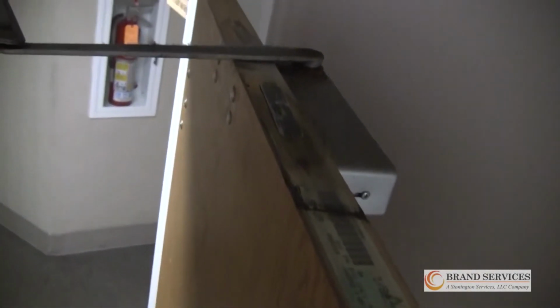First we verify that either or both the door and frame are labeled. Doors and frames are required to be labeled and listed. This stairwell door is required to be 90 minutes or 1.5 hours. Frame labels are not to be painted over. Here you'll find a frame label that has been painted over and is almost unreadable.